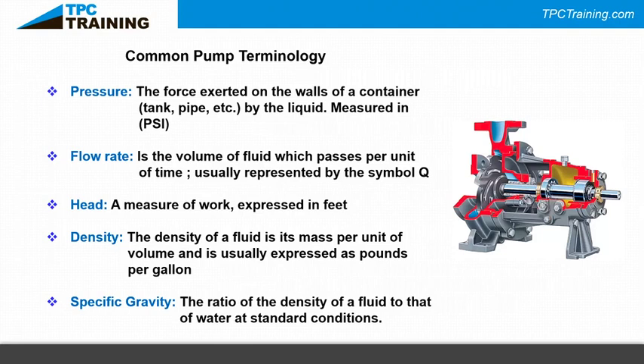That head-to-pressure relationship only differs for fire pumps, which are rated in gallons per minute and PSI discharge pressure by design. In everyday industry, pump specs show gallons per minute and feet of head — not PSI. Density is the other factor: a cork floats in water because it's less dense; a stone sinks because it's denser. Density is typically expressed in pounds per gallon — a gallon of gasoline weighs less than a gallon of water.